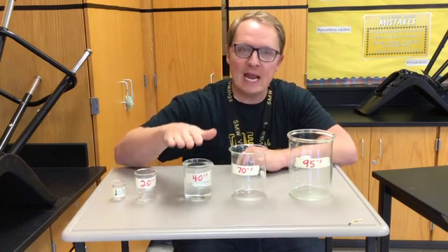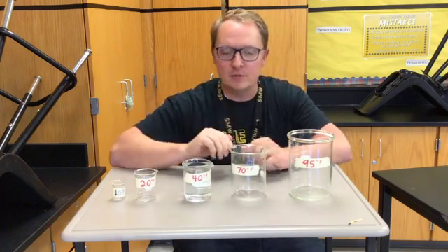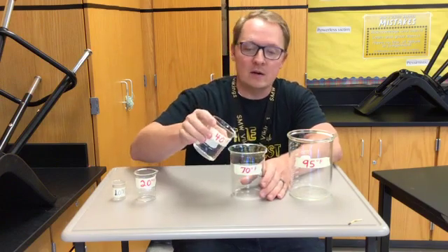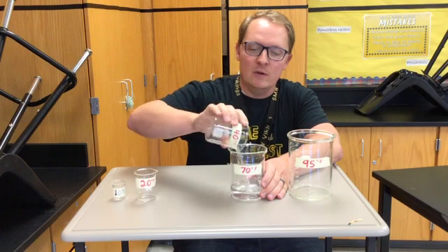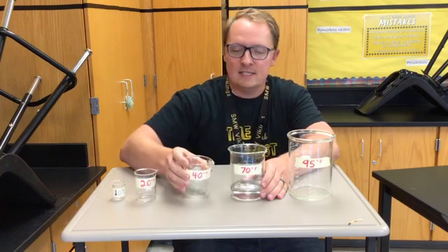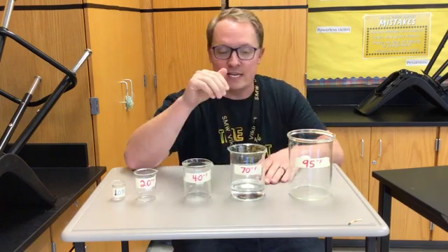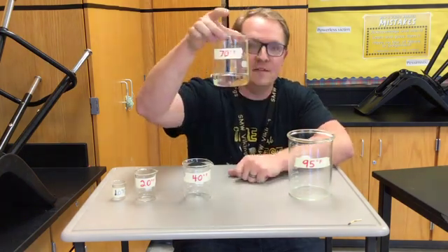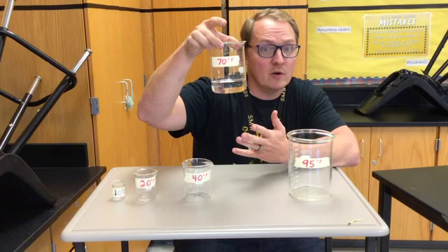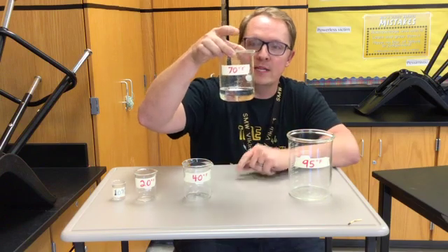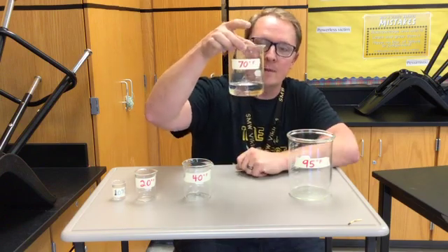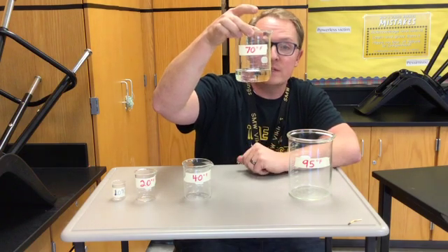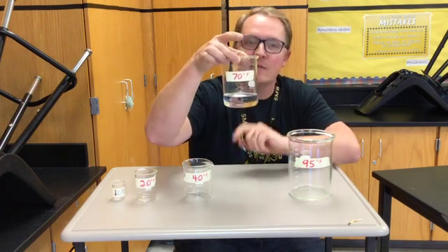Watch what happens when the air begins to warm up. If the temperature outside goes to 70 degrees, but the moisture in the air stays the same, then what happens is the air at 70 degrees has a greater capacity. It can hold more moisture, right? But this beaker is clearly not 50% full. It's the same amount of water vapor as before. The only thing that's happened is the air is warmed up, and now we're at something maybe around 15%, 20% relative humidity, but it's the same amount of moisture.